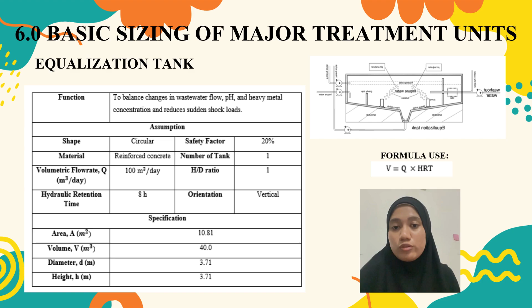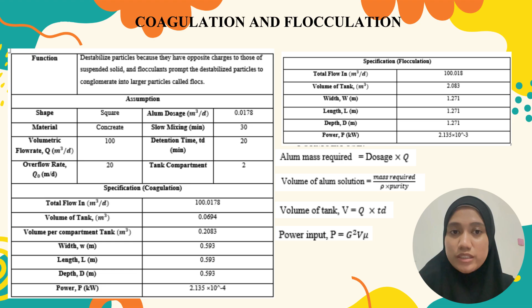After equalization, the wastewater enters the coagulation and flocculation units. For the coagulation tank, a short retention time of about 1 to 5 minutes is normally used because rapid mixing is required to disperse the coagulants. The tank volume is calculated using the flow rate and detention time. For the flocculation tank, a longer retention time of around 20 to 30 minutes is selected to allow particle aggregation and floc formation. Using the same volume equation, the required tank volume and dimensions are obtained.